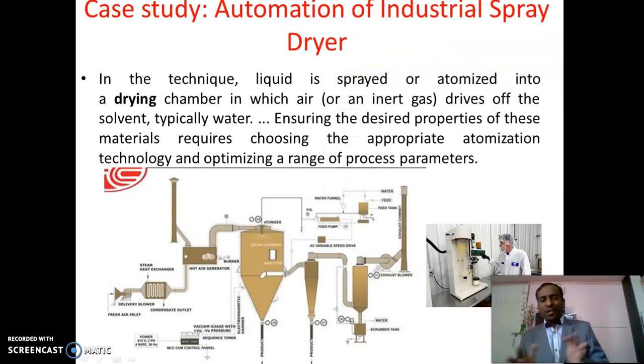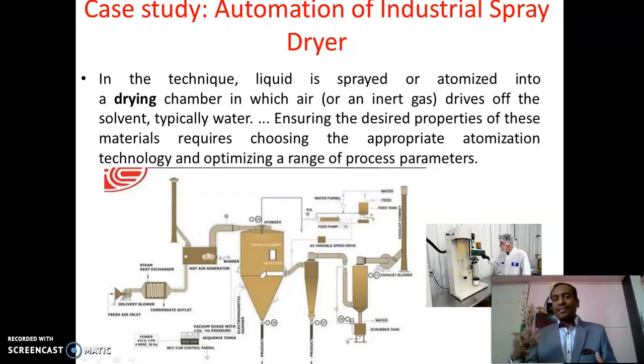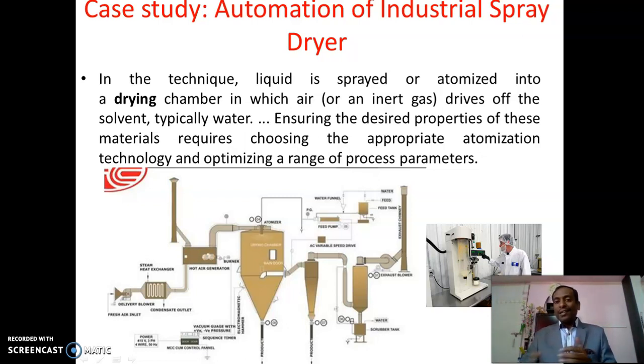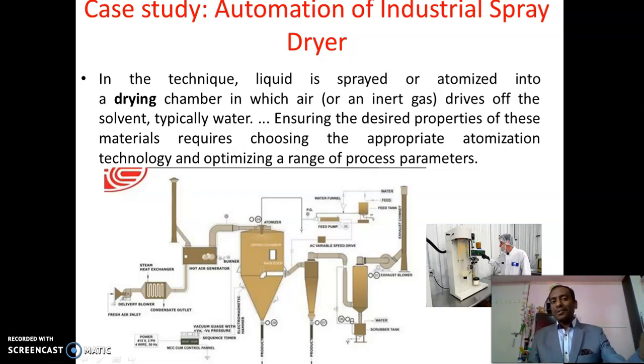One case study is automation in the spray dryer, which is used to dry products to obtain porous substances, increase solubility, and improve drug stability. In this technique, liquid is sprayed or atomized in a drying chamber where air or inert gas drives off the solvent — typically water. Choosing appropriate atomization technology and optimizing process parameters allows you to set parameters according to your need. Fully automatic spray dryers are now available where you only set inlet temperature, outlet temperature, and flow rate, and the AI software manages the entire process.